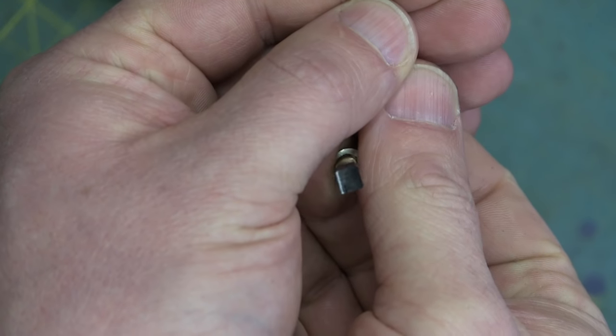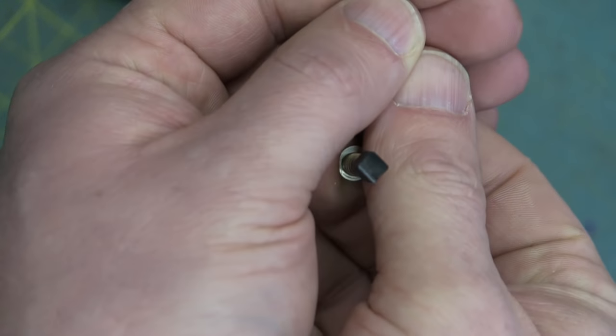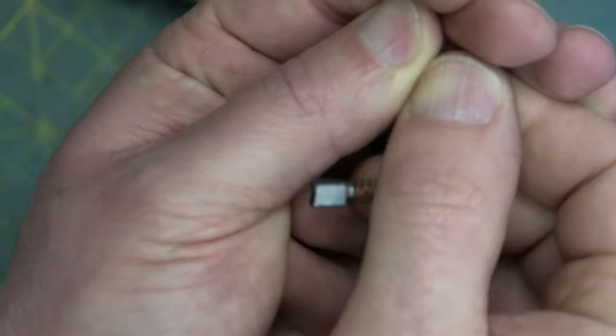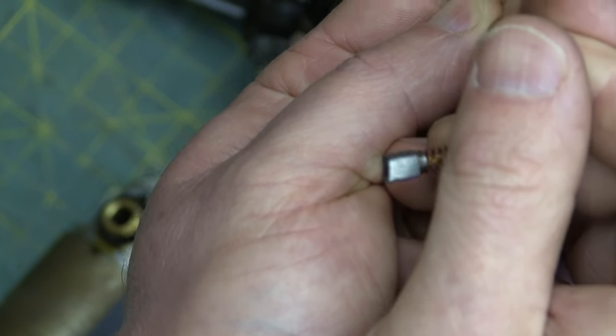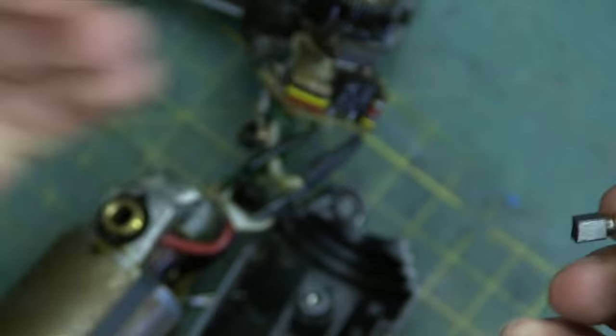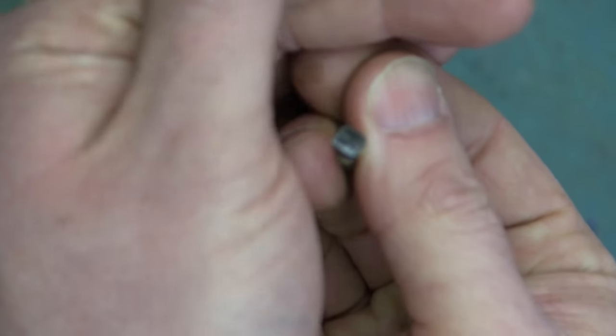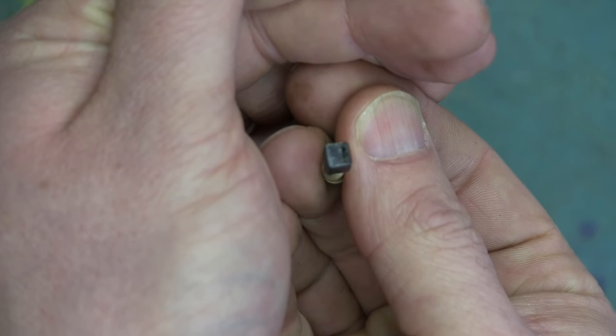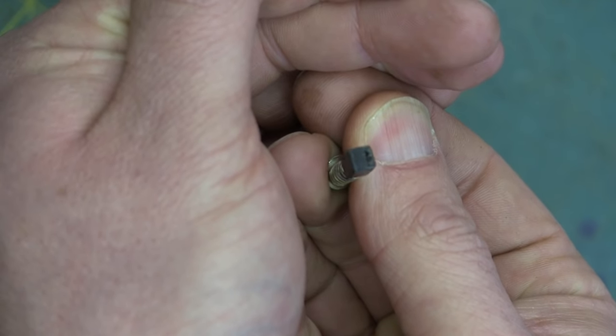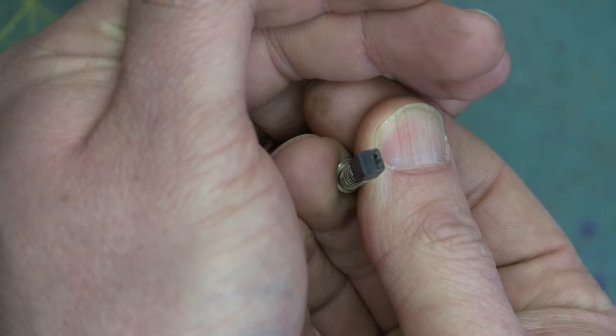We can see on that right-handed side there are some burn marks and glazing on the other side. So that got fried and look at the wear pattern. That's cocked over in the brush holder. That's not real good. The other one's not as bad but still has that same burn mark on it. Where it must have stalled out on the commutator. You see that one even better, where it stalled out on the commutator and just would have been arcing and sparking away.